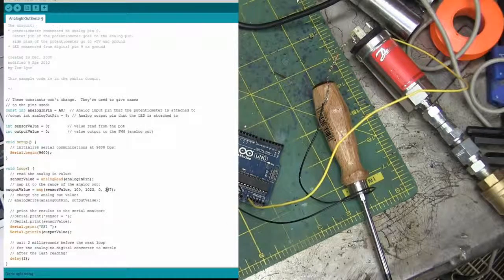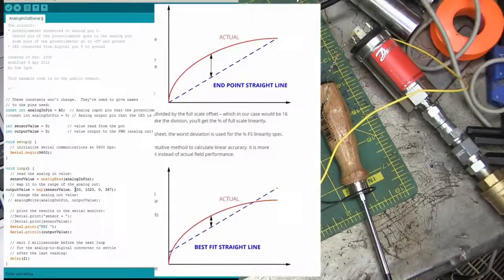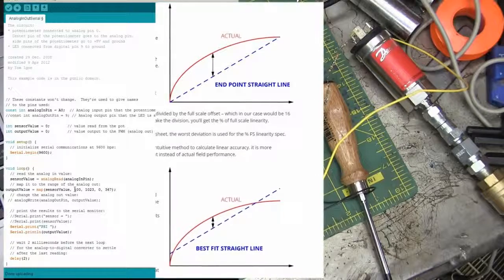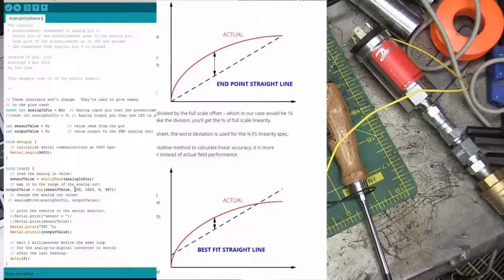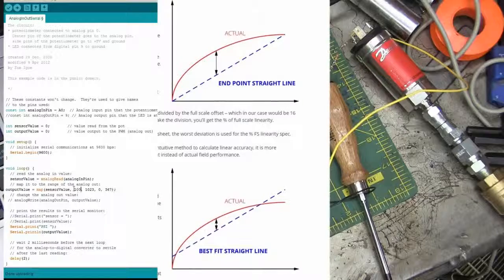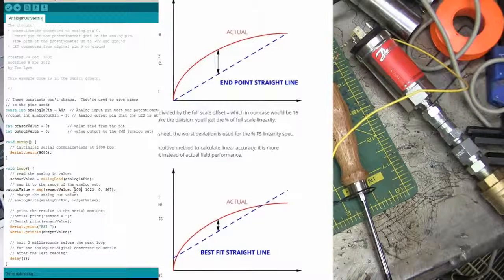How do we know it's 367? That's the top of the scale, 25 bar, and 0 is the bottom of the scale. This number is a best guess. You can calculate it, but it's probably better not to, because there's some non-linearity in the sensor at the bottom of the scale. It's better just to guess, you just sort of mess around.